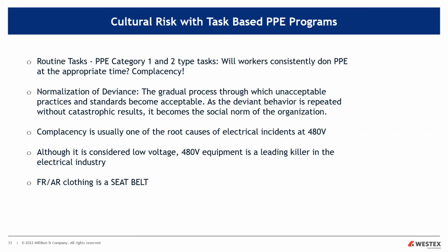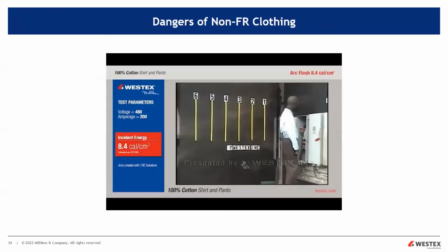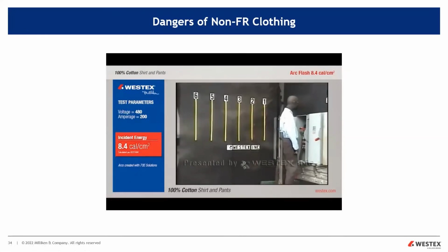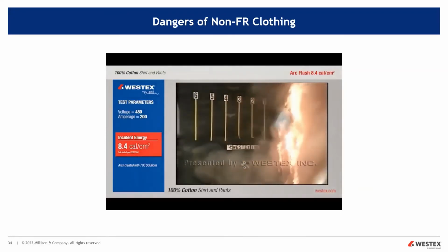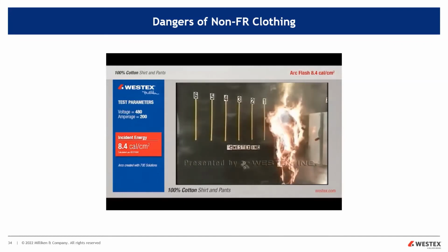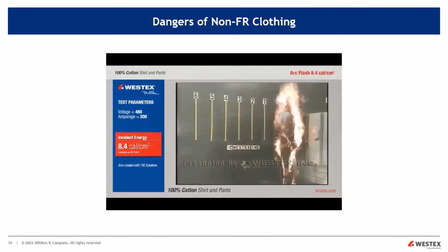If it's a task-based thing, a lot of times those aren't worn. Out of sight, the bag of safety sits in the locker, sits in the truck. Out of sight, out of mind, no help being a preventative measure as well as a protective measure. So what can happen if you have a situation where you didn't don the PPE at the appropriate time? You're wearing your natural fibers underneath. It's just a routine task. What can happen? This is cotton clothing in a category 2 arc. However, this arc is going to do something different. It hits the ground and rolls out a good 10 feet, and the garments are instantly on fire from the shoes right on up. The entire mannequin. This is a very, very fierce fire, obviously. You're going to suffer massive, if not total, body burn.